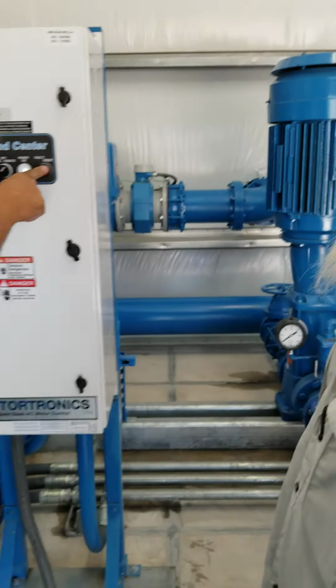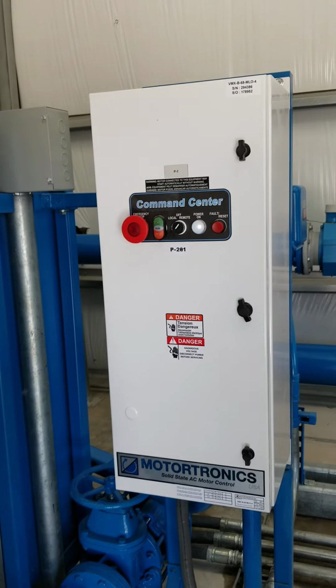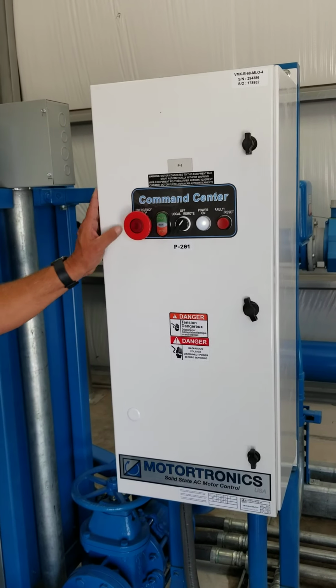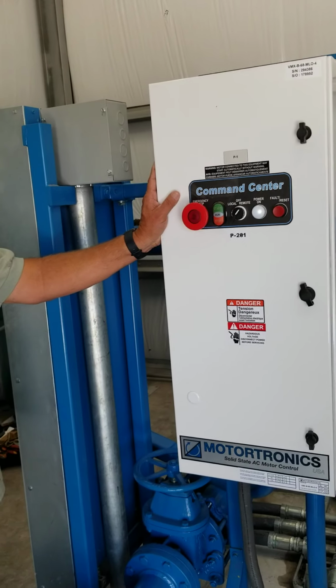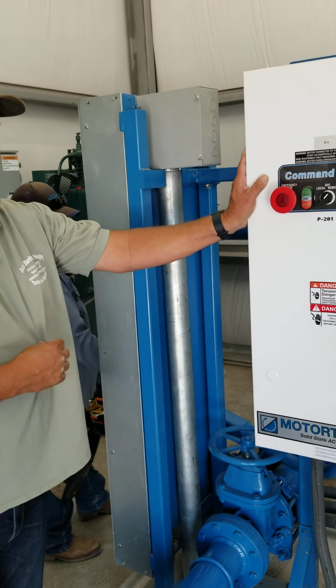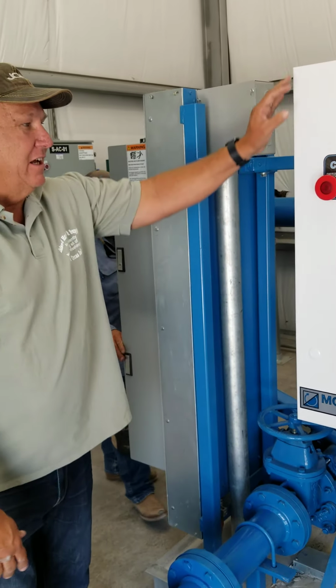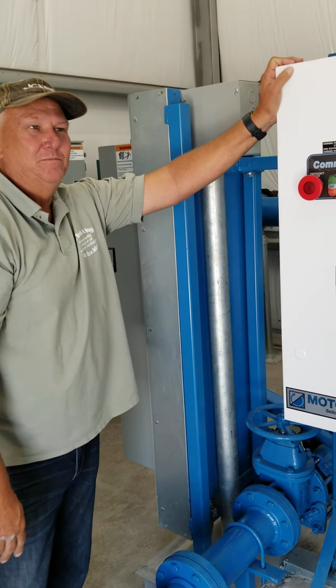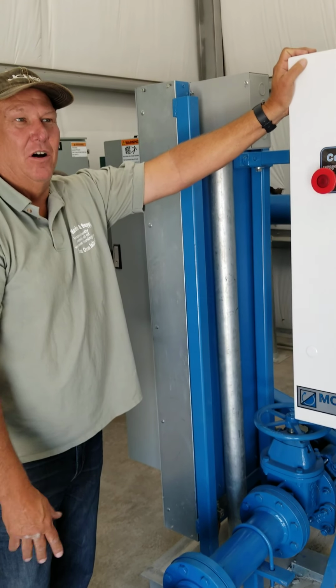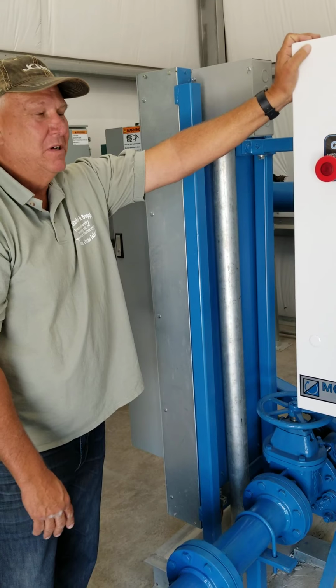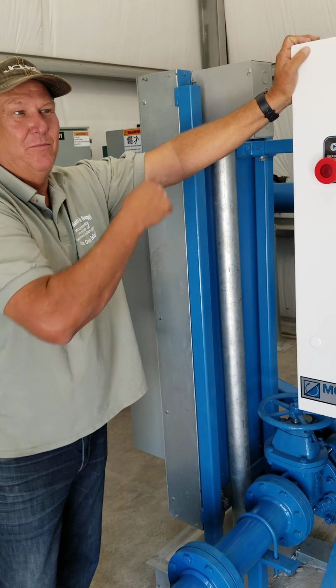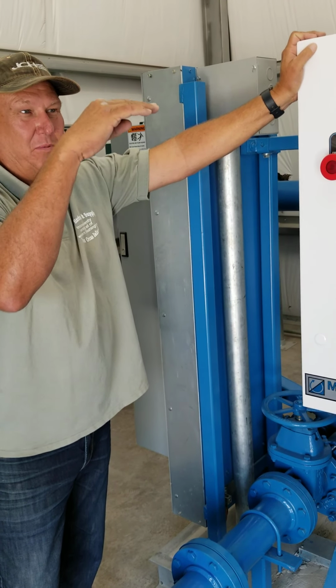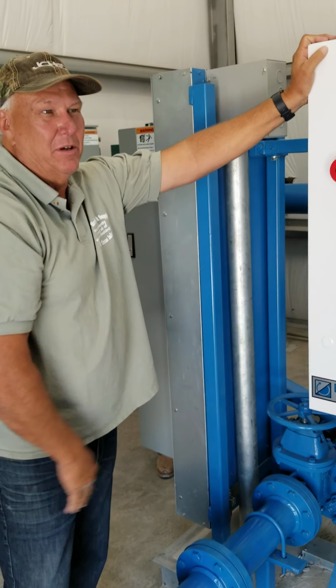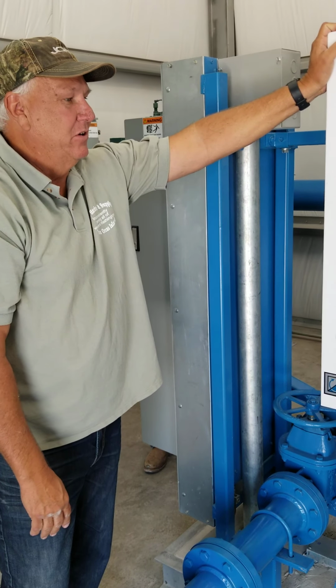So they got emergency stop here. If you ever got into a situation where you had to run it in hand, you'd have to stay here and just use one pump. You can't even walk off because it generates so much pressure. And then you send a guy in the back to make sure the water's right where it needs to be. Monitor it, and then take the air valves. I mean, it'd be a pretty big deal.